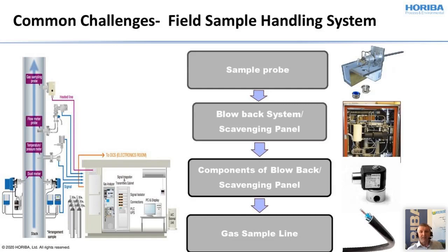The sample line should be heated with proper tracing to maintain the dew point of the sample line and to keep true representative samples to the analyzer. Also, it is to ensure that there is no leakage in the complete line from the probe to the analyzer module.